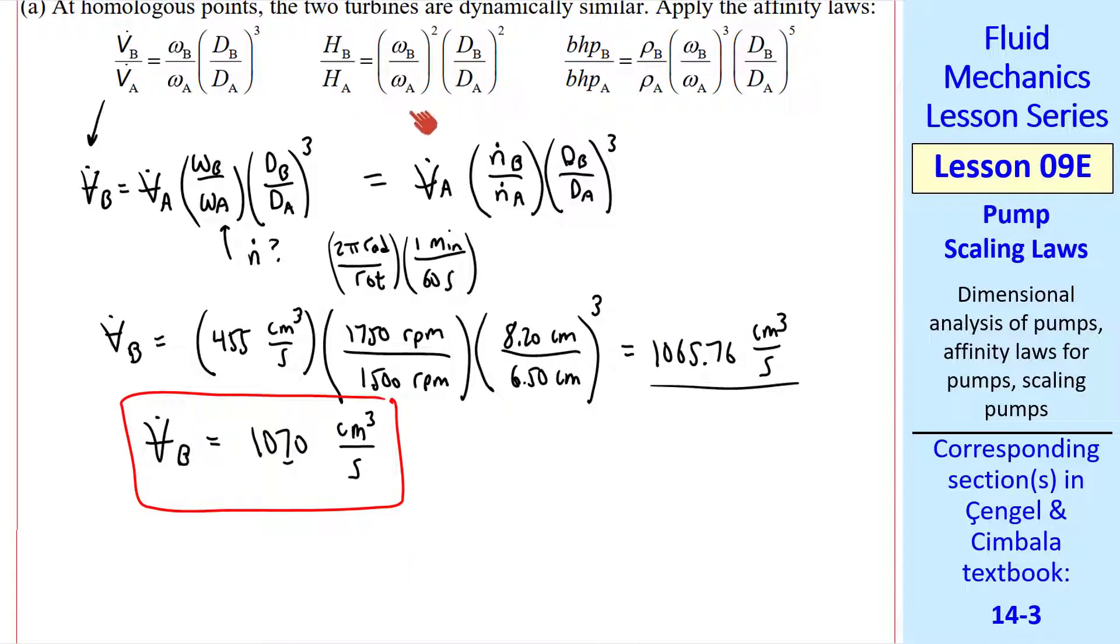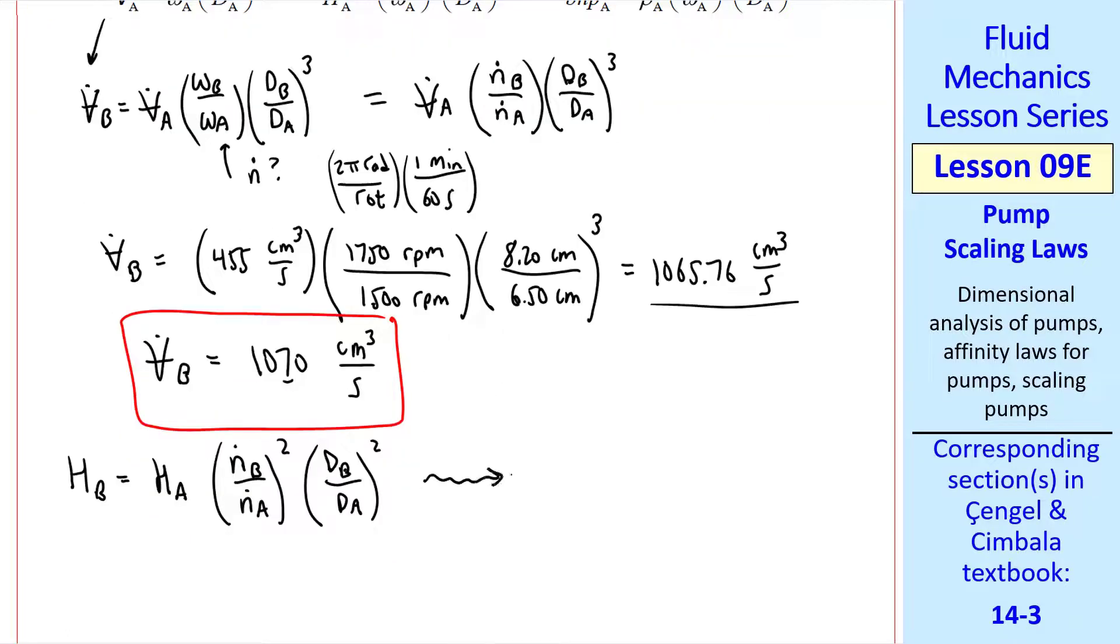Similarly, using the second affinity law, we write HB equal HA, N dot B over N dot A squared, times DB over DA squared. I'll spare you all the details. When you plug in the numbers, we get HB equal 3.12 meters, which is also more than twice as much as the net head of pump A.